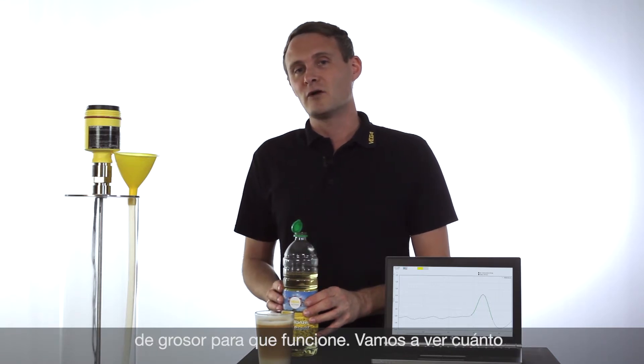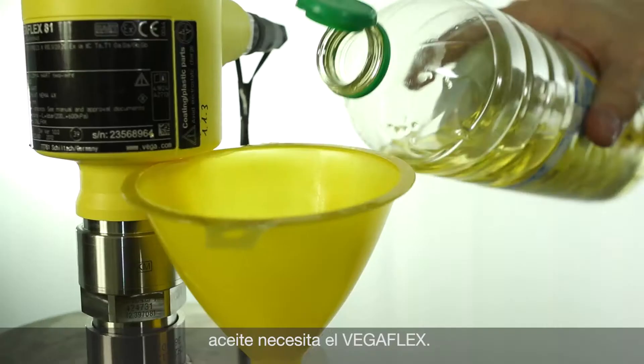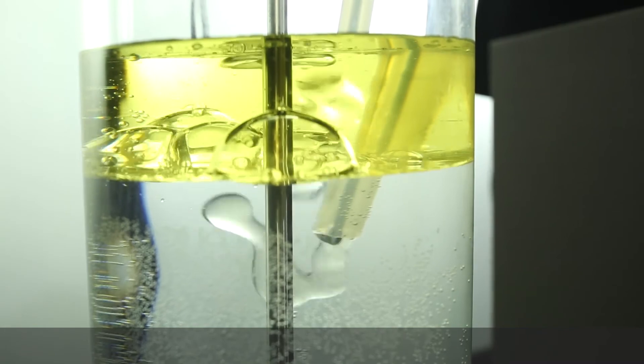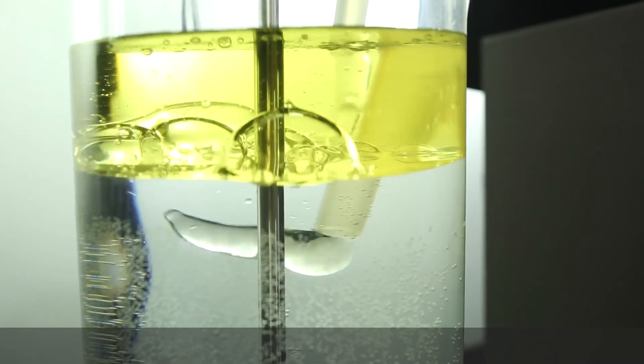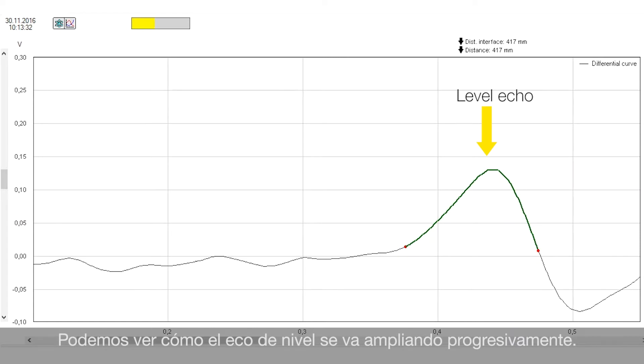Let's see how much oil we need for the VegaFlex 81. You can see now on the echo curve that the level echo is getting wider and wider.